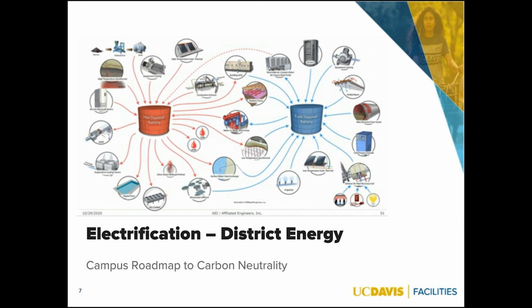It may be too small to see everything, but what it shows is that initially we're recovering heat from the buildings, and there are some easy ways to do even more. For example, we're going to look at closing down our airside economizers and extracting more heat out of the buildings. It's counterintuitive, you typically want to use those economizers to reduce mechanical cooling, but if you pull more heat out of the buildings when you have a heat recovery chiller or heat pump, you can get a significantly greater amount of heat in the winter.